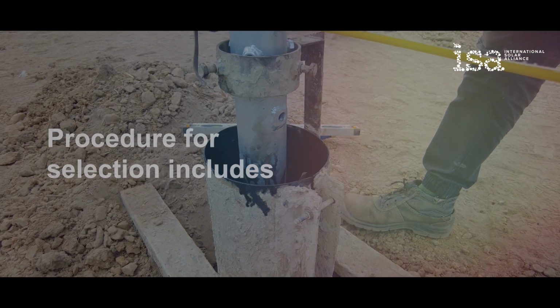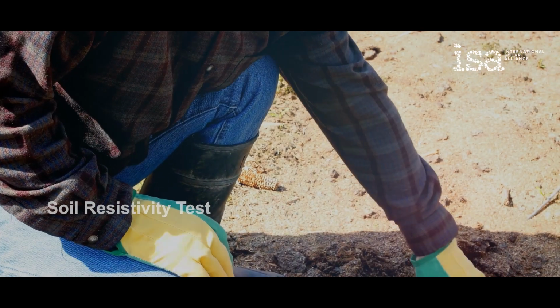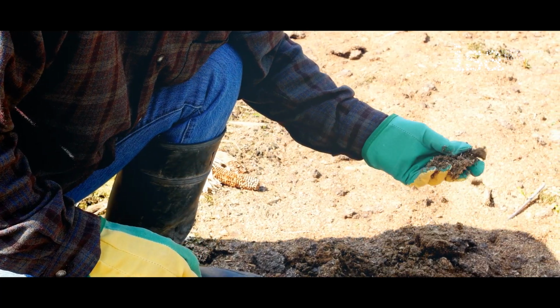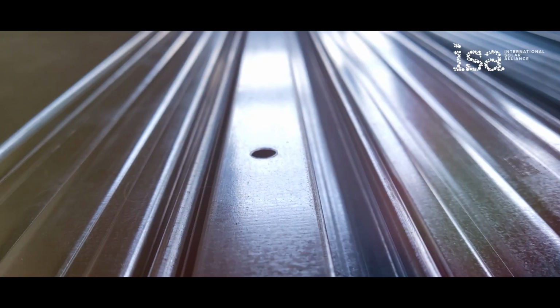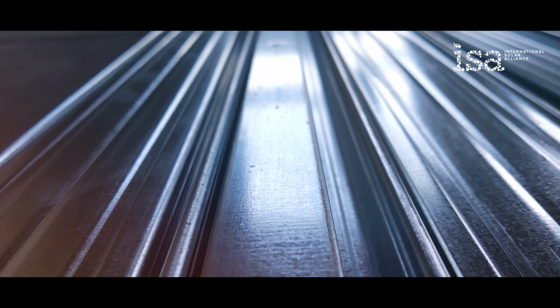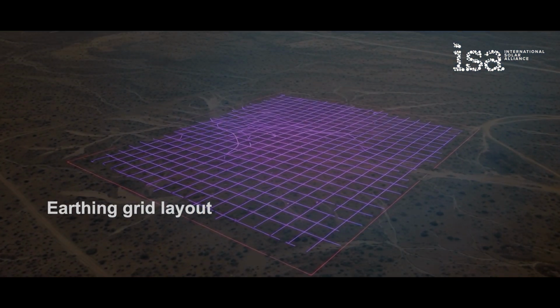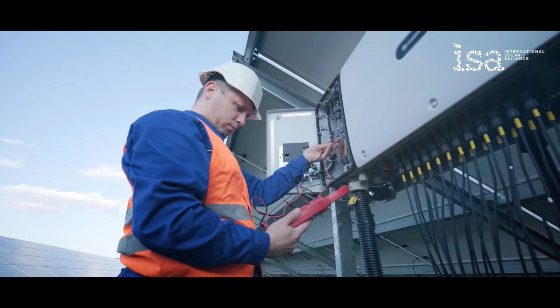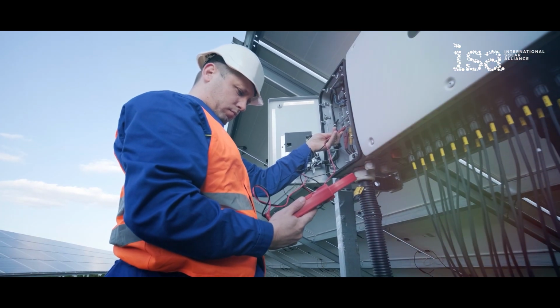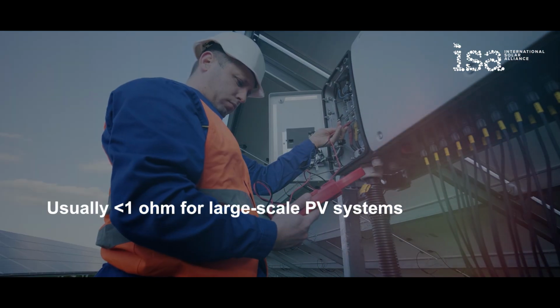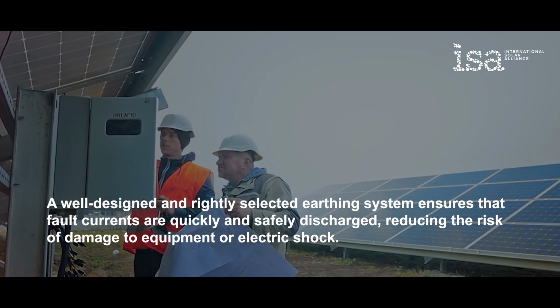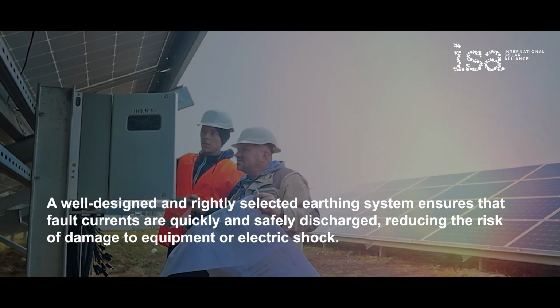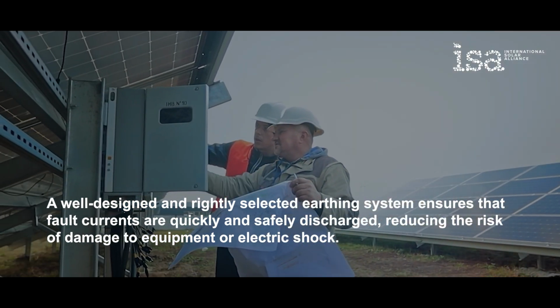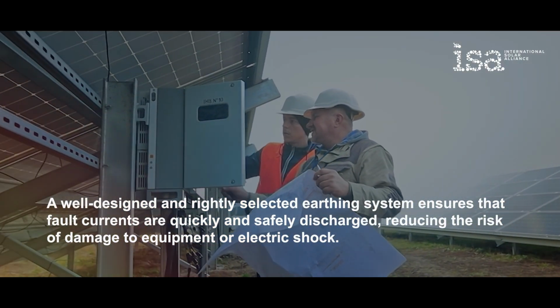The procedure for selection includes performing a soil resistivity test using the Wenner or Schlumberger method, selecting the appropriate electrode material such as copper, galvanized iron, or chemical electrodes, designing the earthing grid layout, whether single-point, multi-point, or mesh type, and testing and verifying that earth resistance values are within acceptable limits, usually 1 ohm for large-scale PV systems. A well-designed and rightly selected earthing system ensures that fault currents are quickly and safely discharged, reducing the risk of damage to equipment or electric shock.